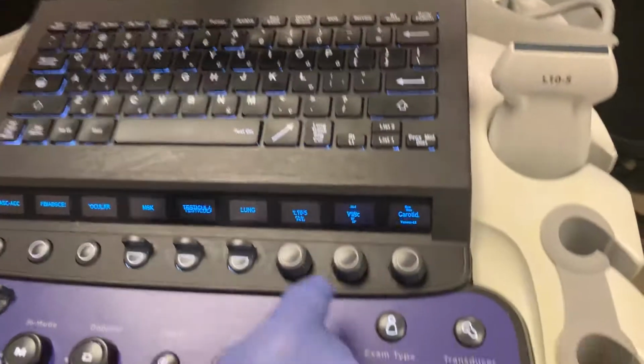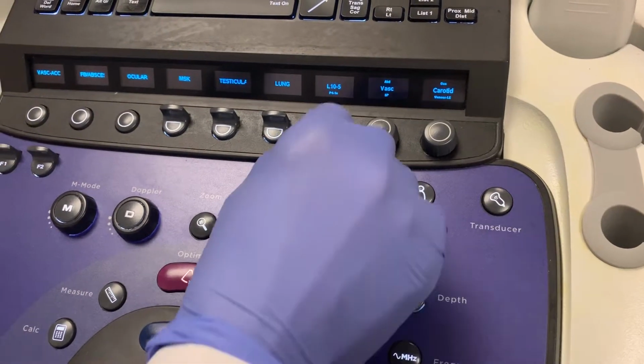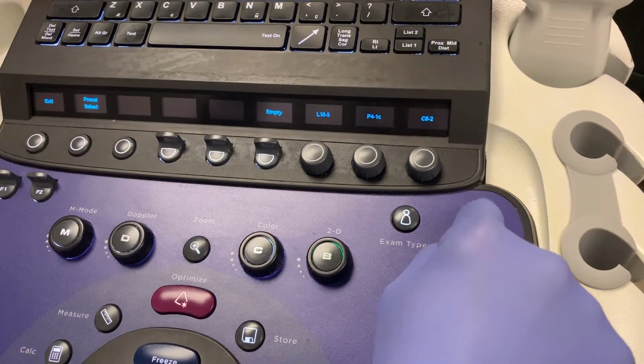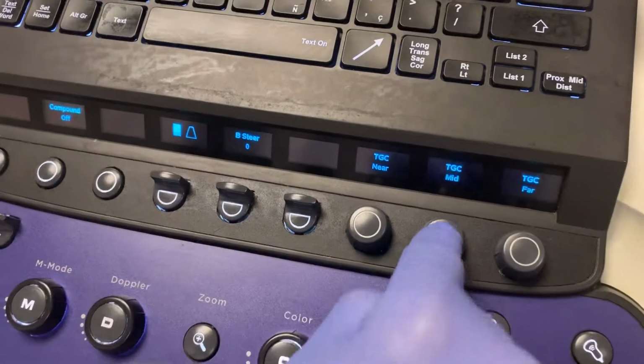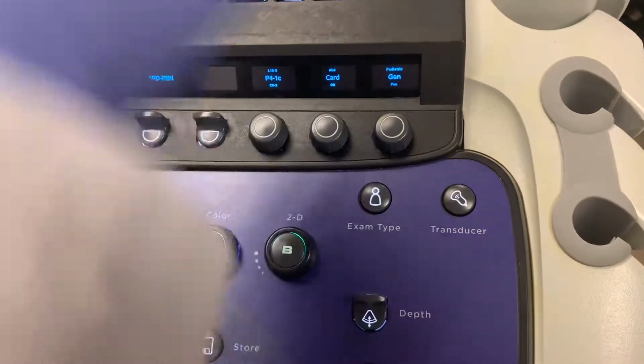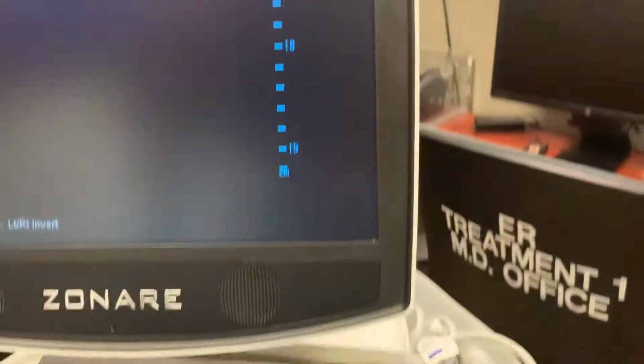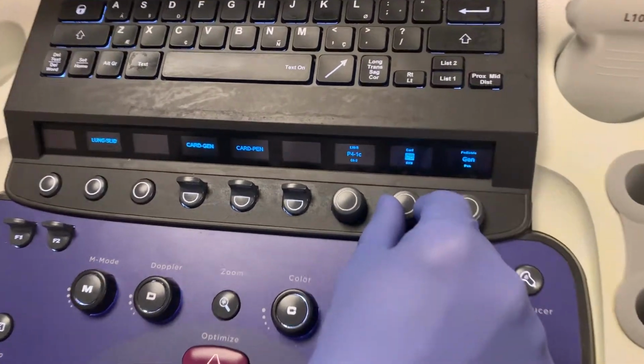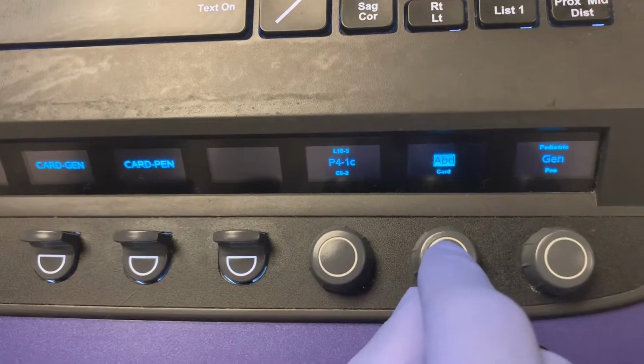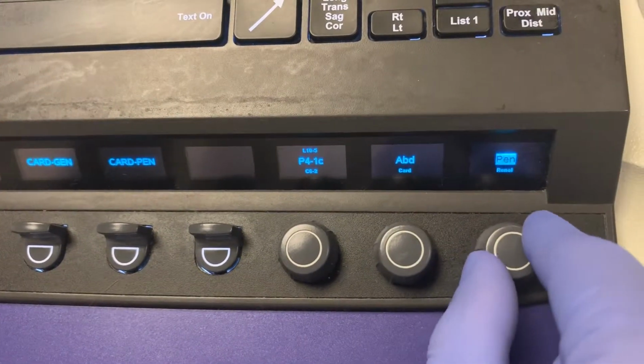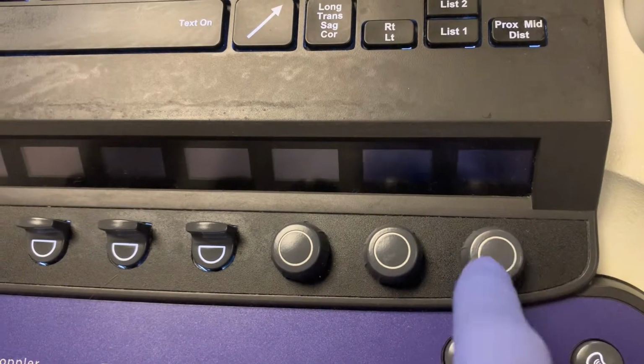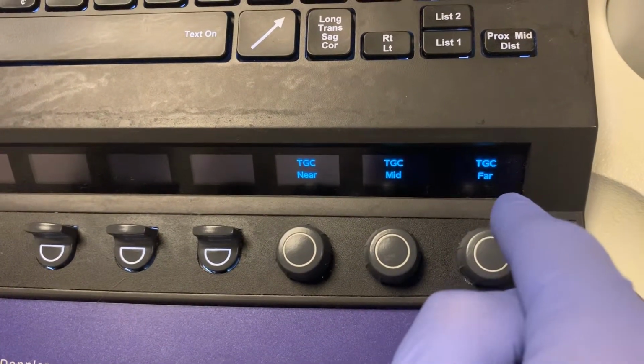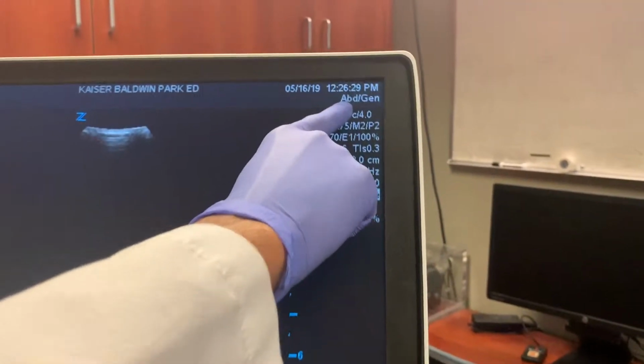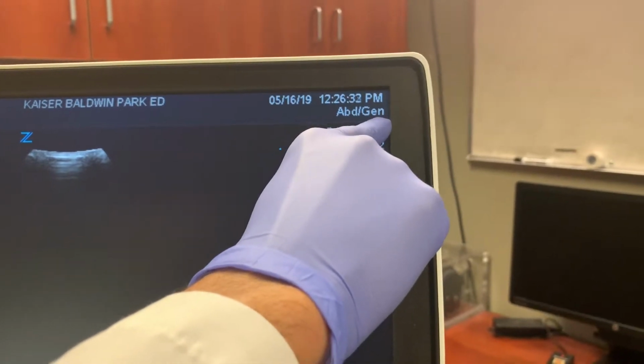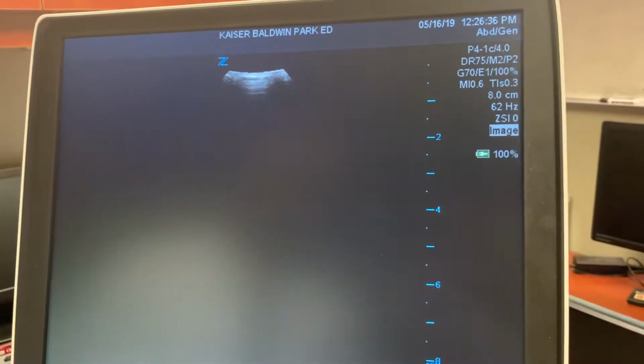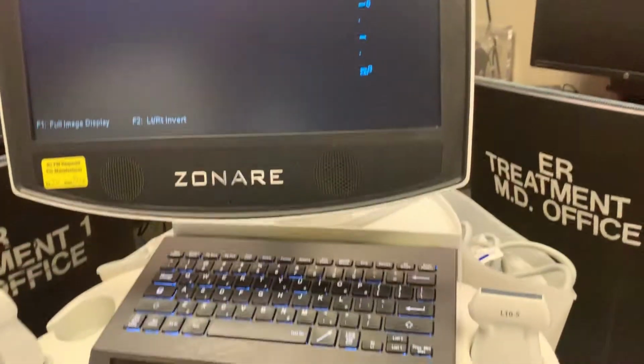All right, now the other thing you have to do is decide the exam type. So let's go back the old way. We'll hit transducer. We're going to go to the phased array, and it defaults to cards general. But you can change the exam type in, again, two different ways. One, we kind of showed you. Let's say I want now to do an abdominal exam, so I'll roll it to abdomen and hit select, and then here I'll roll it down to general. General is probably the only thing you're going to use on this last setting. And now you look up here, and where it said before card gen, it now says abdomen gen. All right, so now your settings are more useful for an abdominal exam.